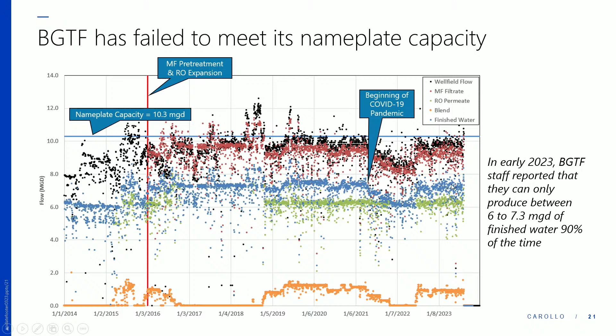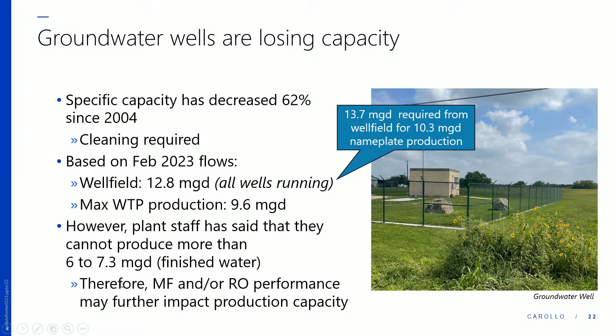The first reason is that the groundwater well field is losing capacity. We talked about this last time. The wells are plugging, they need to be cleaned. If all of the wells are running, so we have no wells available for standby, the well field can make 12.8 million gallons per day. And that would result in a nameplate production capacity of 9.6 million gallons per day. And just a reminder again, we need 13.7 to make the nameplate production capacity. So the well field is part of the reason. But 9.6 with all the wells running, there's got to be some other reasons that plant staff are only making 6 to 7.3 million gallons per day. We're going to look at the MF and the RO as reasons for that.